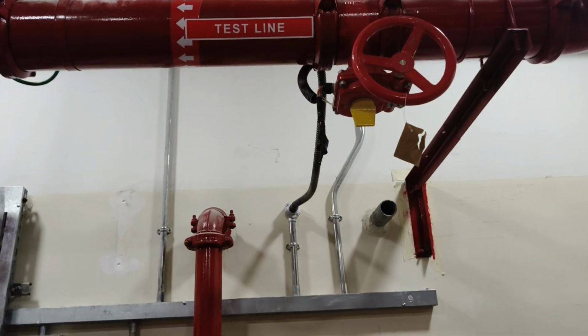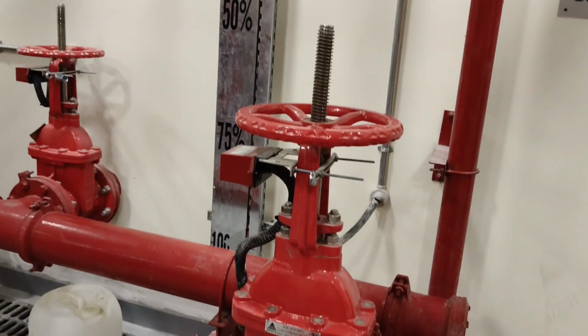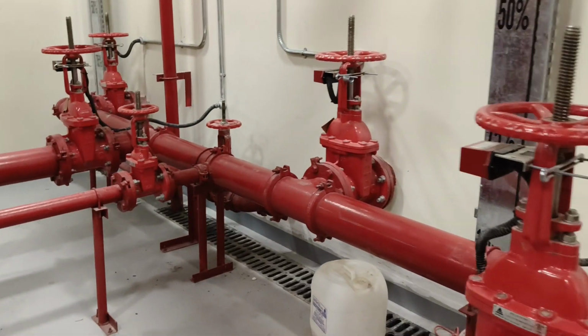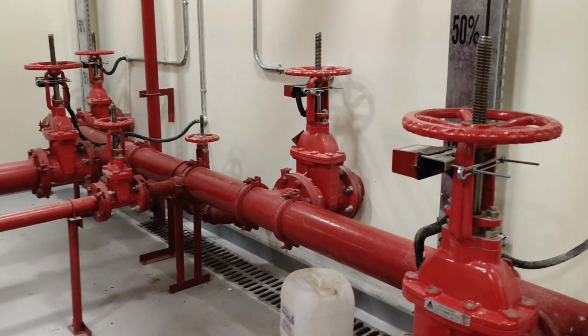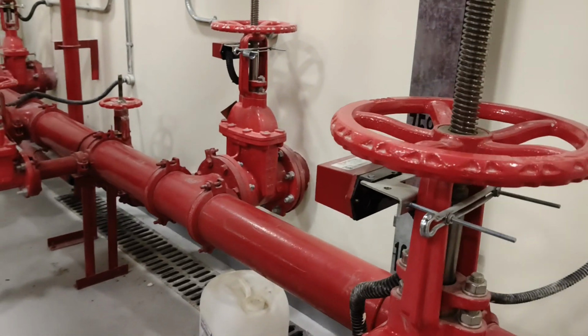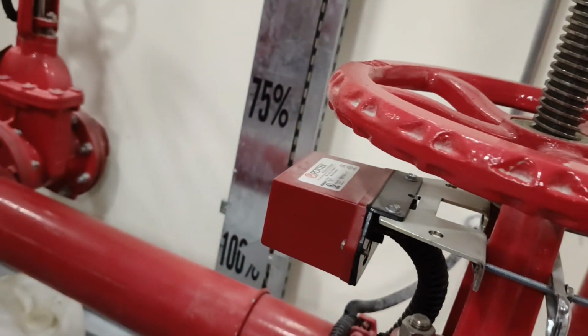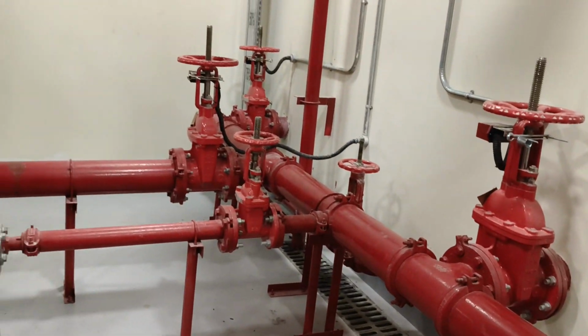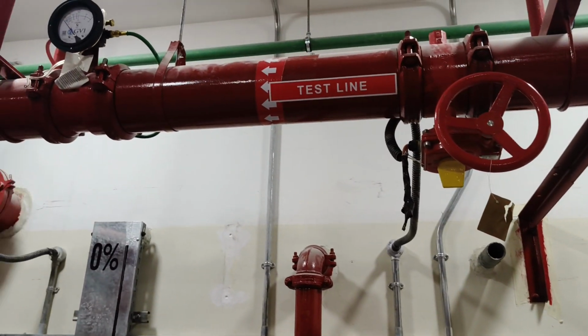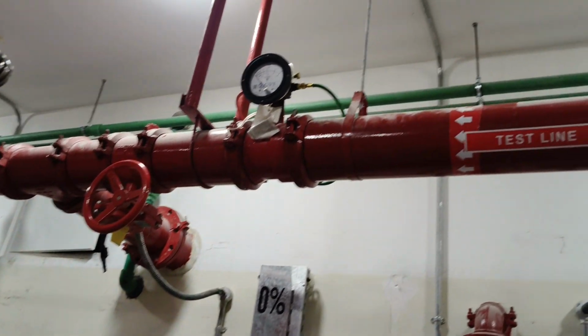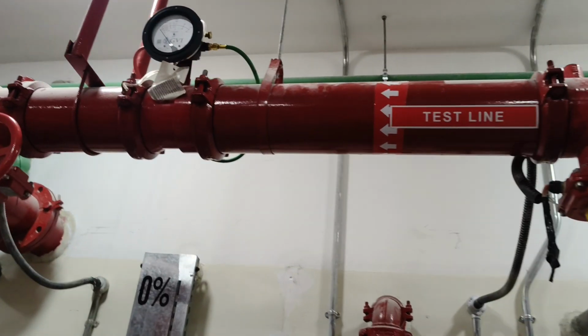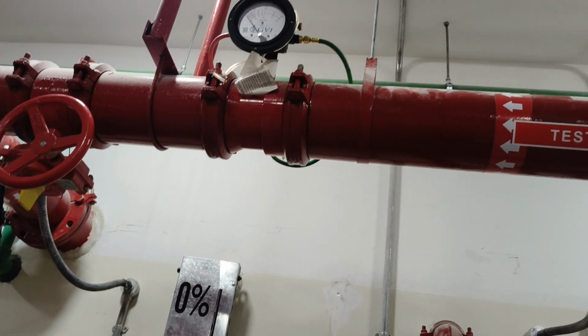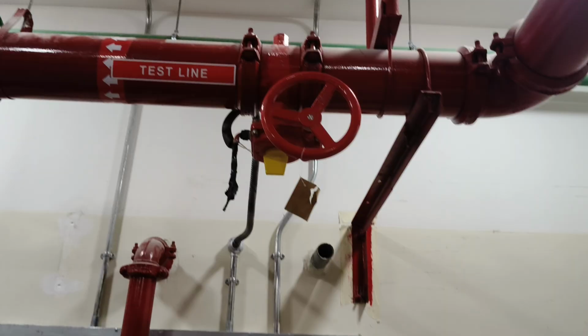As per this valve, the suction valves all have to be normally open. As per the normally open condition is how you're going to wire the tamper switch, either NO or NC. So the bypass and the throttle valve, and that's the flow meter. The flow meter is 1000 GPM, US GPM.